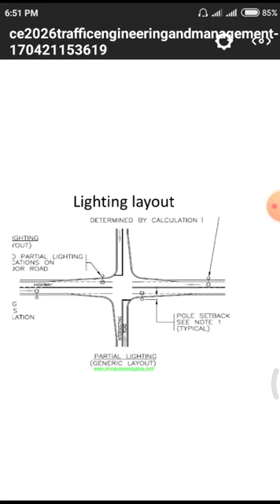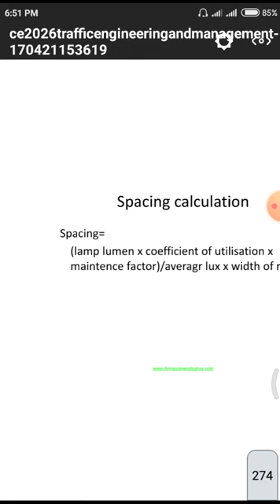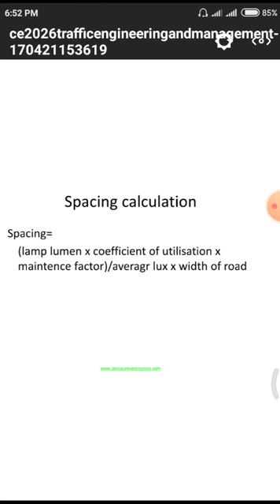It is the utilization curve. That means the distance of the particular roads and the utilized lines. All over India we have some utilization curves for these street lights. This is the formula for calculation of spacing between two poles. Spacing equals lamp units, that means lumens, into coefficient of utilization into maintenance factor, divided by average lux into width of the road. That is the formula for the calculation of spacing between light to light.